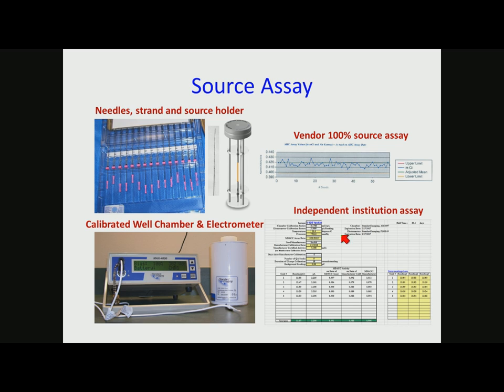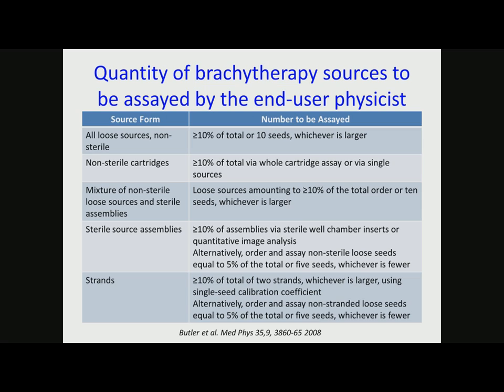And then internally, we do our own QA as well, randomly with 5% of the seeds because we use strands, and we check our QA. And within 3%, we're okay. There's a nice article by Wayne Butler from the Brachytherapy Subcommittee of AAPM in 2008. They're saying if you use all loose seeds, non-sterile, you can do 10% like before. Nothing's changed there. Same thing in the non-sterile cartridges. If you have a mixture of non-sterile loose seeds and sterile assemblies, they get 10%. If you use sterile source assemblies, that's the strands, or this, these are both more or less the same thing. It's 10% assembly via sterile well chamber inserts, or quantitative image analysis.